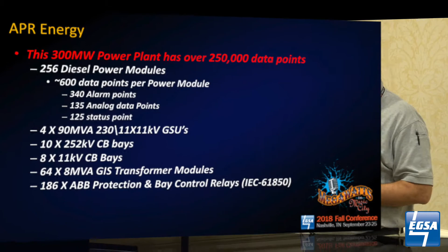There's a wrong number there on the bottom. We've got about 286 ABB protection relays across the whole site to protect all the medium voltage and high voltage systems. You can't watch that on monitors and look for problems - it's physically not possible. You cannot watch 256 generators on a job site, you can't put enough people out there. So this is the whole reason why remote monitoring works: collect all the data, analyze it with analytics in a data historian, and generate actionable events before you actually have an event.